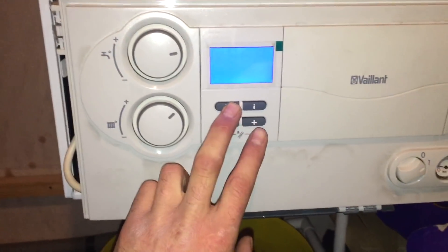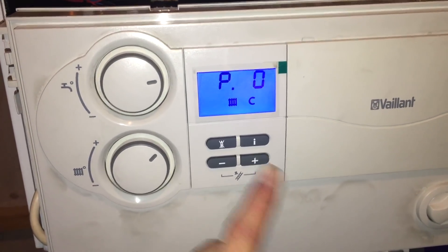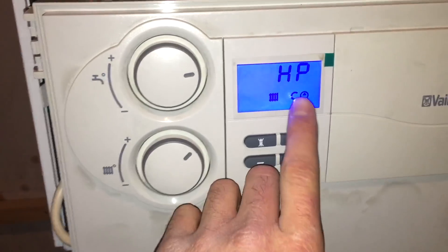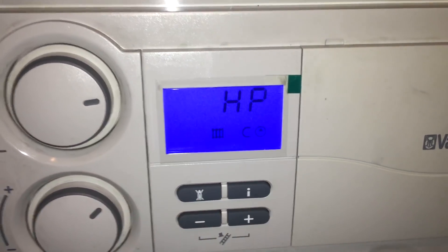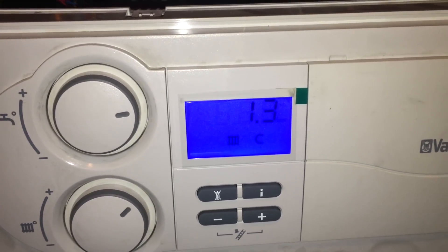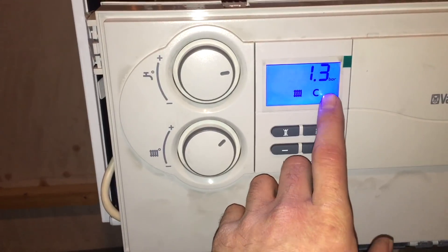Let's do that again. For F75 issues, with the boiler on, press reset, hold the plus, get the two dots flashing, get P0, press i — that's now running the pump for 20 seconds and stopping it for 20 seconds. With the pump running — that's the pump symbol there — we have 1.6 bar. Now the pump has stopped, let's see what it says: 1.3 bar. So it went down by 0.3 of a bar.